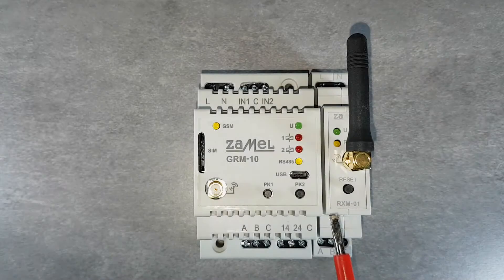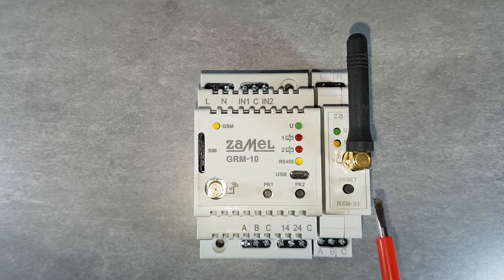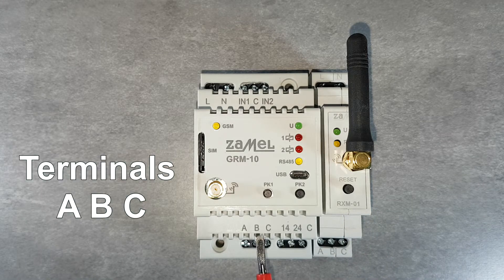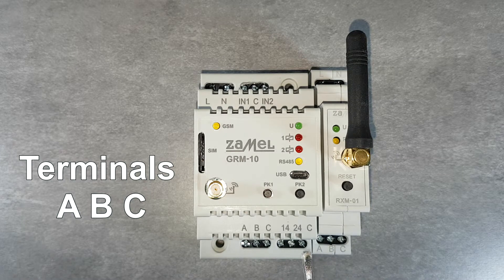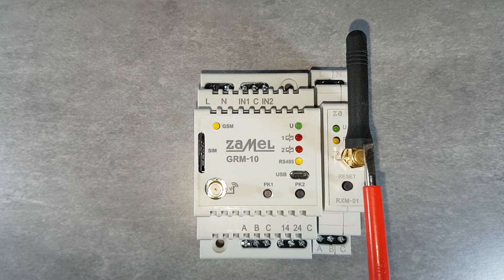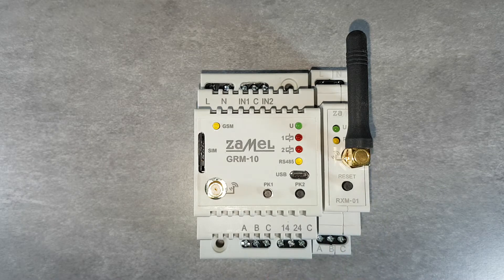The Modbus protocol outputs have also been integrated in the GRM10 controller. They are for connecting, for example, the RXM01 translator module. Connection between devices is carried out using the Modbus bus marked as A, B, C lines. The GRM10 controller sends commands on the bus to the RXM01 converter, which broadcasts radio signals in the Exta Free standard. This solution allows controlling Exta Free receivers using user-defined SMS text commands.